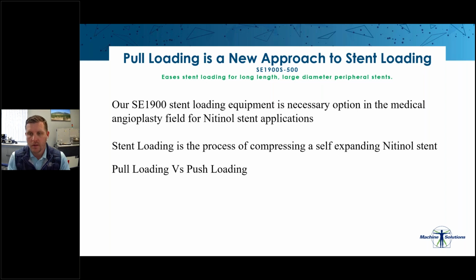By pull loading, you take the strain off the distal crowns of the stent and distribute the forces needed to load the stent evenly across the delivery catheter shaft. This allows crimp pulse to reduce radial compression forces, and the stent will move easier throughout the introducer sheath. By pulling on the catheter from the proximal end, you eliminate the possibility of damaging the distal end of the stent.